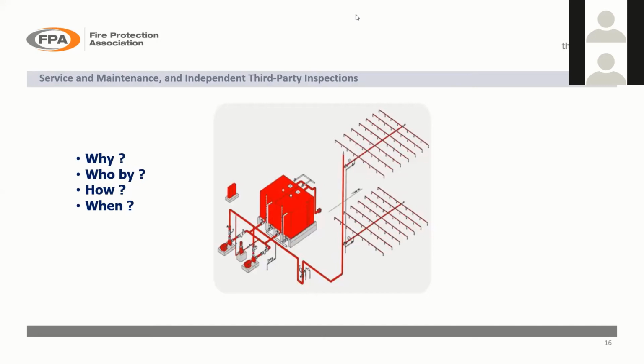I've put a sprinkler system on the screen there, a diagram of a sprinkler system for people who perhaps don't come across them every day. Obviously, sprinkler contractors are very familiar with this kind of thing, but what you can see there is a couple of sprinkler pumps and a water storage tank and sprinkler pipework and the sprinkler heads. And obviously, in a big building like a warehouse, you could have several systems, but just one water supply. And obviously, that water supply then is critical to the system. So some parts of the system really are more critical than other parts, and will obviously need greater maintenance than other parts. But if you look along the pipework runs there, you've got sprinkler heads on the end of those ranges, and they are just as critical as the pumps themselves. Obviously, if one of those fails and the fire develops, you could lose the building in much the same way that if your water supplies don't work.